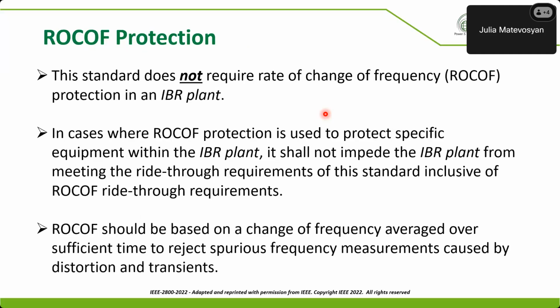ROCOF, again, as I mentioned earlier: the standard does not require that if the ROCOF is more than 5 hertz per second, then the plant shall trip. It simply says that for ROCOF up to 5 hertz per second, the plant shall be able to ride through, right? So if it is necessary to protect the plant and any equipment within the plant from severe ROCOF, then just make sure that whatever mechanism is chosen to declare that the ROCOF was higher than a certain threshold allows the plant to meet the ride-through requirements of the standard. The last bullet is sort of important.